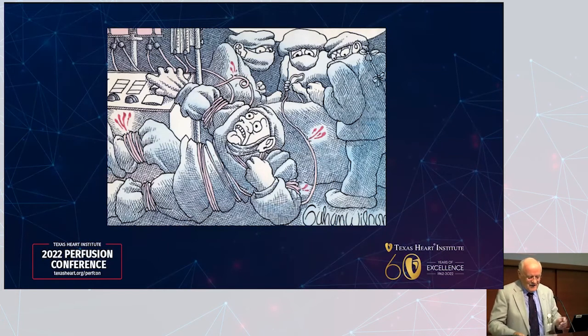For hemodilution, they originally primed pumps with 20 cc per kilogram of D5RL — or as low as 800 milliliters. Eventually the priming protocol changed to consist of other solutions. They also used one-quarter, three-eighths, and half-inch tubing strategically in various parts of the circuit to reduce overall prime, with and without blood — just as people do today — and eventually other crystalloid solutions. It has been rewarding in recent years to see perfusionists bringing back techniques used back in the 1970s.